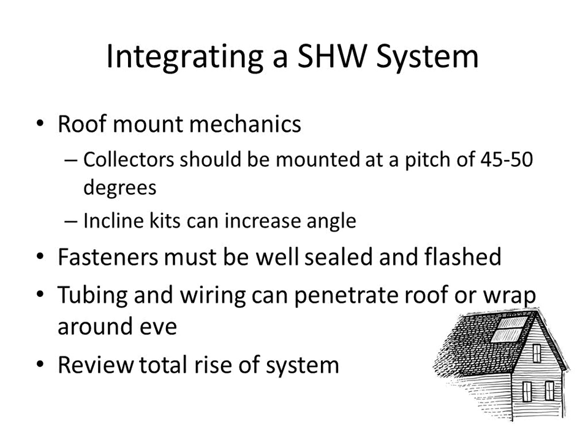So one of the things to take into account on a roof mount system is to review the total rise of the system. And by that, I mean the distance from your glycol pump to your collectors. Some systems are very sensitive to that and will place pretty strict limits of 25 or 35 feet. Other systems are not, and we'll give you a tubing run and tell you basically the tubing run could be 100 feet, 120 feet. So if you're going up on top of a two-story home and you've got a basement, you may well have a rise of 35 or 40 feet.